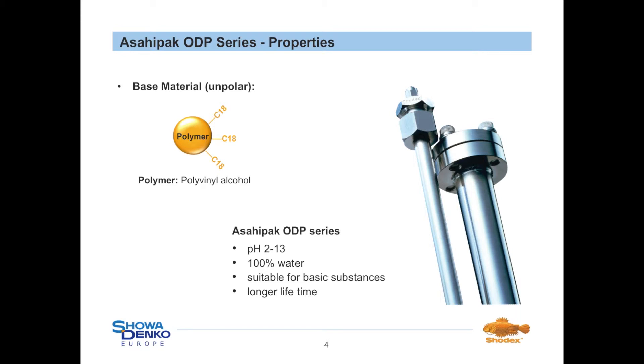The Asahipak ODP series is one of the most important reversed-phase columns in Shodex's assortment. As the stationary phase consists of pure polymer-based C18 particles, the limitations and drawbacks of traditional silica-based reversed-phase columns are overcome. C18-modified polyvinyl alcohol particles are used as the stationary phase. Polymer-based columns, especially the ODP series, can be used within an extended pH range from 2 to 13, whereas silica-based ones only up to 7.5. Additionally, 100% water can be used as eluent, and due to the absence of free silanol groups, simple analysis of basic substances is possible without high salt concentrations or ion pair reagents. The polymeric material also offers 2 to 3 times higher lifetime compared to silica-based columns.